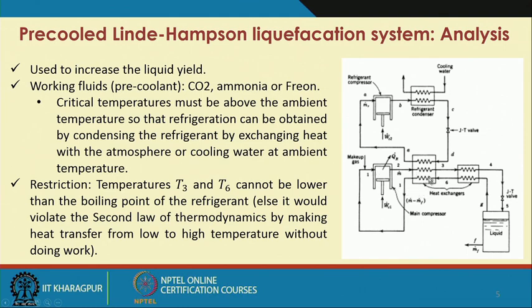Here, instead of a two-channel heat exchanger, we are using a three-channel heat exchanger. The third stream in this three-channel heat exchanger is coming from the auxiliary refrigerant system. This refrigerant system is again based on a simple Linde-Hampson system. The refrigerant helps to cool the process stream further. We are trying to use cooling water from the ambient or ambient air to cool down this refrigerant, so we are not trying to increase our cost of refrigeration. Here again we have a J-T valve to get this cooling.